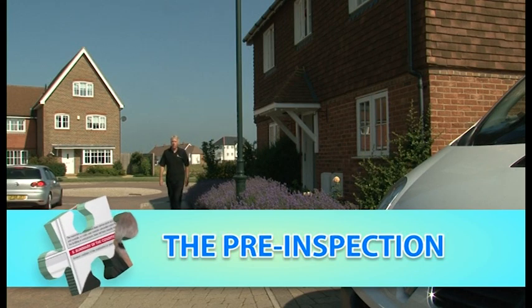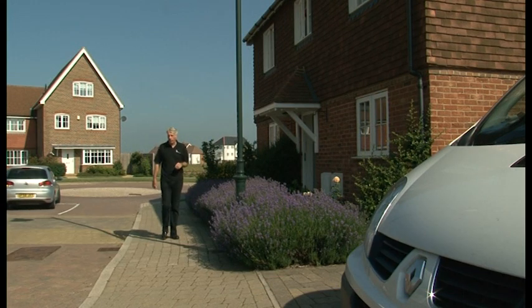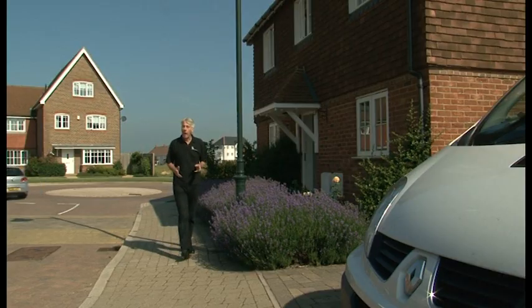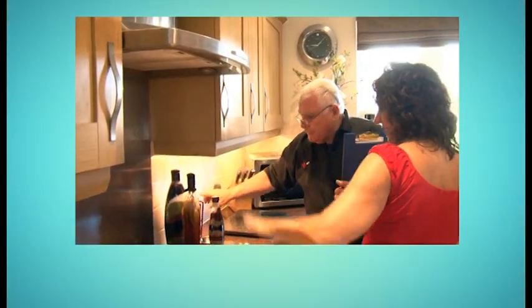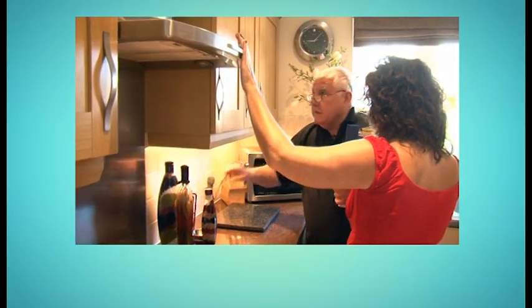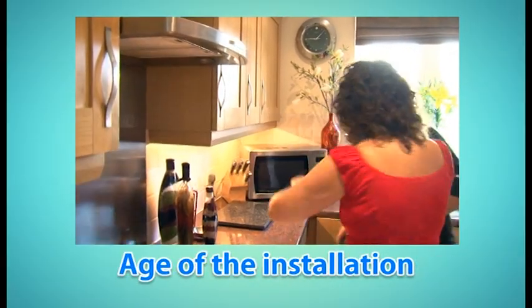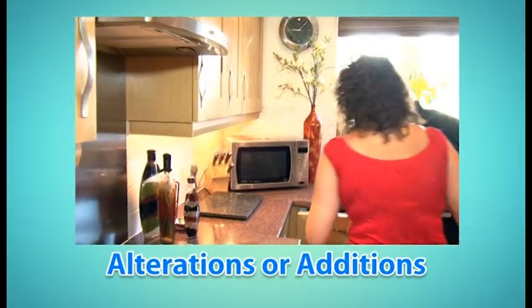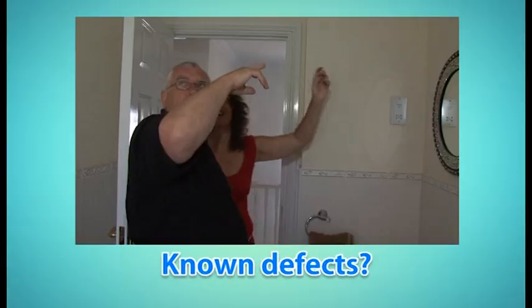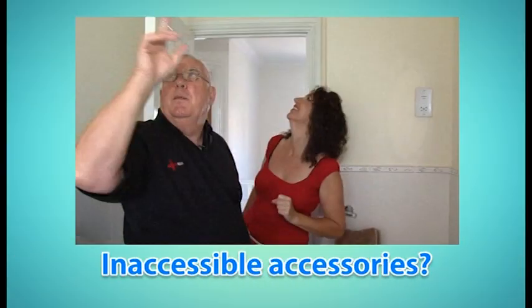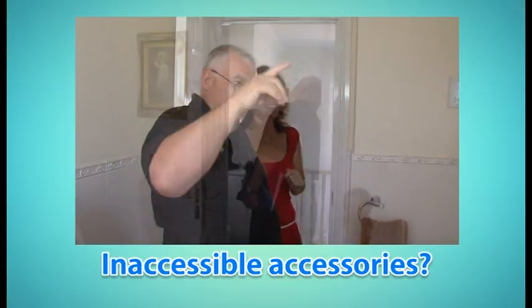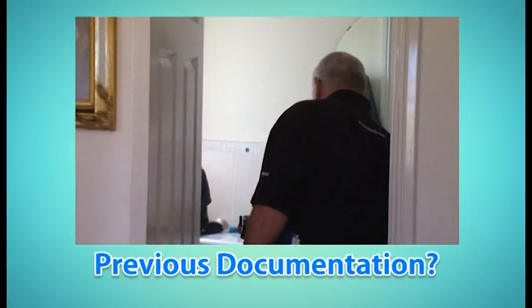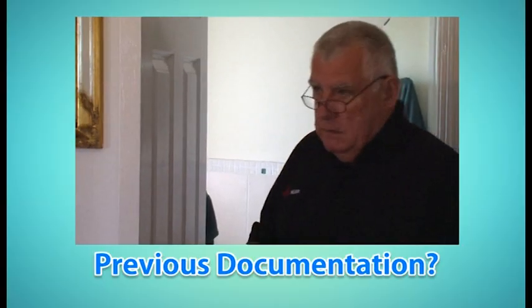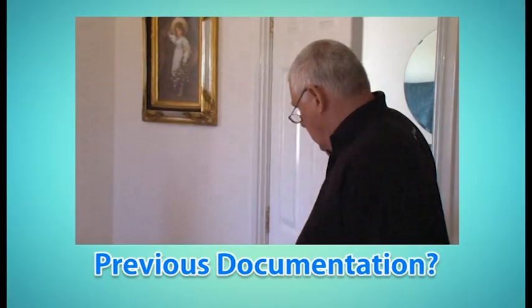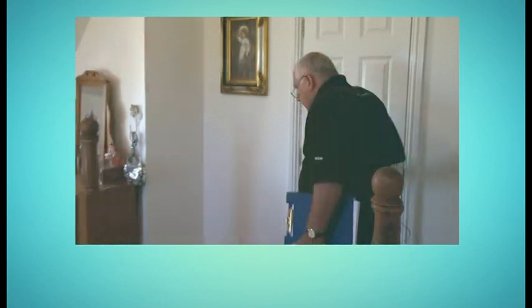We're at the property which is about to undergo an electrical installation condition report. It's been requested because the house is about to go on the market, and Tony's inside having a chat with the existing owner to find out some more information about the property, including the age of the electrical installation. Have there been alterations or additions? Are there any known defects? Are there accessories that are inaccessible because they're behind heavy furniture? And are there any previous documents relating to the installation? For example, an electrical installation certificate or a periodic inspection report.